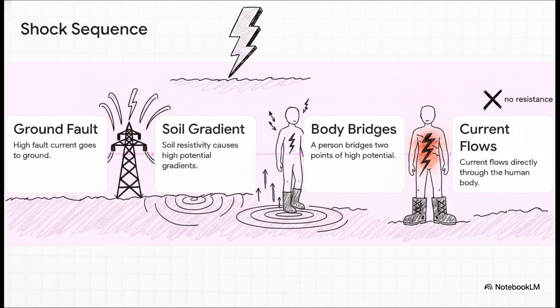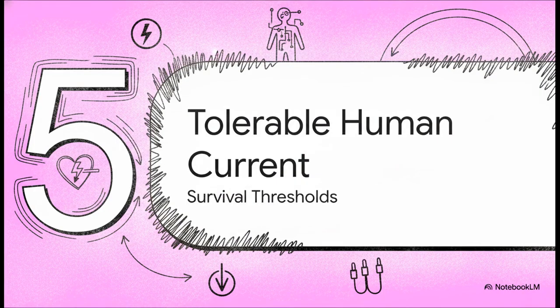So walking step by step through the exact sequence of a fatal accident, it looks like this. First, a high fault current goes to ground. Second, the resistivity of the specific soil creates high potential gradients right at the surface. Third, a person happens to be standing there and bridges 2 points of high potential with their feet or hands. And fourth, because there's no sufficient resistance, like specialized insulated boots, to stop it, that current flows directly through the human body.